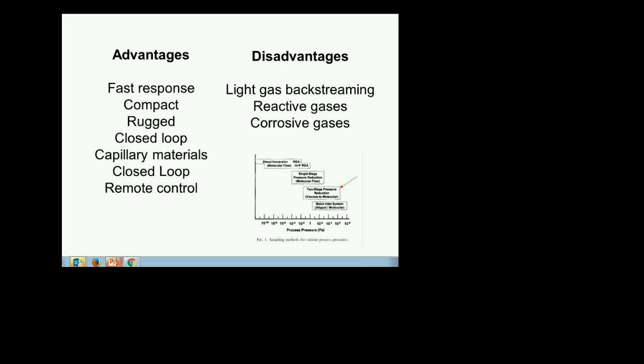Okay, I see the whole picture and I see exactly what we can try to do, because it's a pretty simple gauge, and otherwise I'd have to find a hot cathode gauge and have probably some issues with that too. So you'll have outgassing from that, which means you'll have a lot of crosstalk between the two.